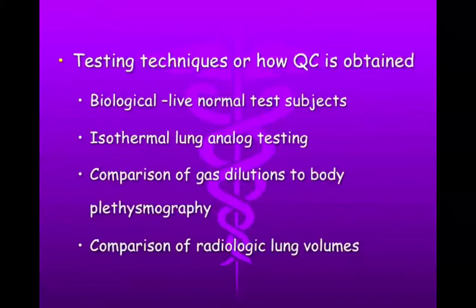We can use what's called an isothermal lung analog testing. We'll talk about that a little bit more later on. We can do some comparisons of dilutions to body plethysmography. We can also do some comparisons with chest x-rays. So, for example, if we were to do a helium dilution test and we compare it to body plethysmography, and we see if there's a normal healthy adult, they really should be pretty accurate and close to one another because healthy adults do not air trap. If it's a normal healthy adult, remember body plethysmography is pretty darn accurate even if they do air trap. You can compare the values you're getting with the machine to lung volumes looking at the chest x-ray.